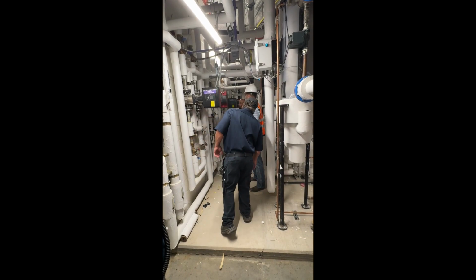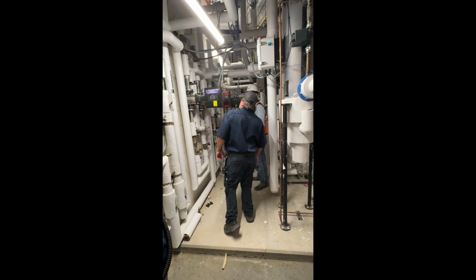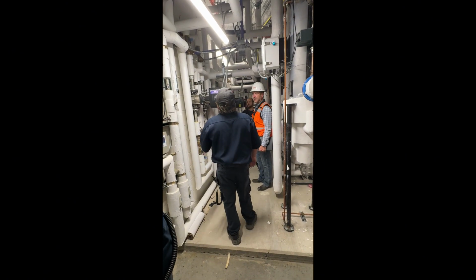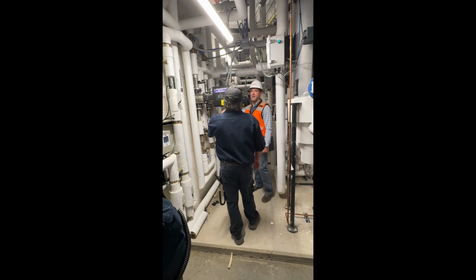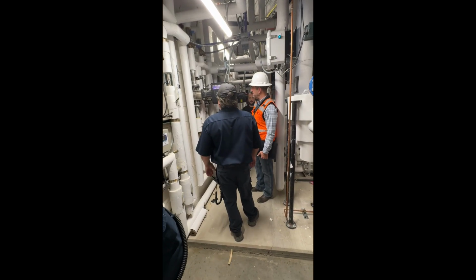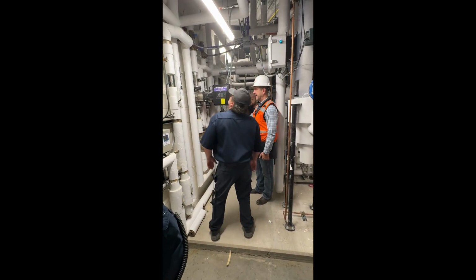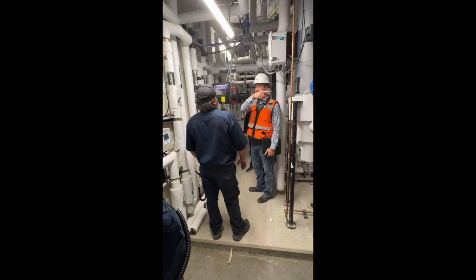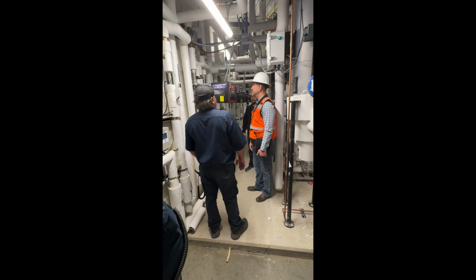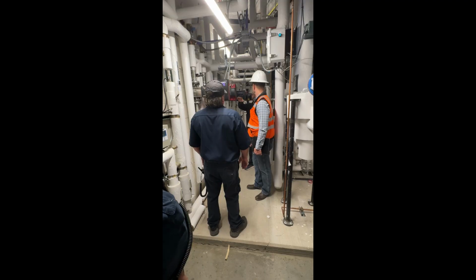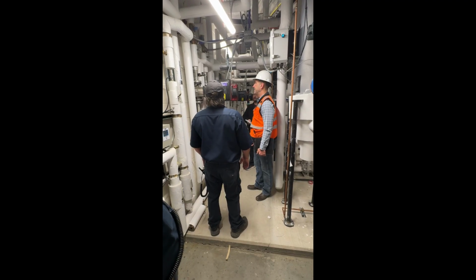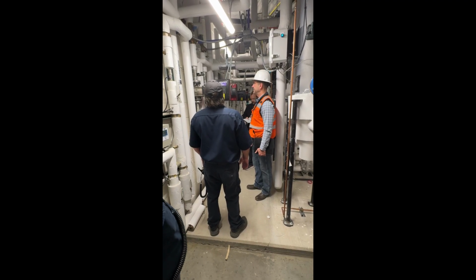I was just seeing that was in there. Yeah, I don't know why that's in there. Those are your return pumps. All that's doing is creating domestic hot water return. Again, the VFD on here is just like the VFD on the domestic booster system. You can always set these the same way if something happens. Yes. Yep. Same exact thing.